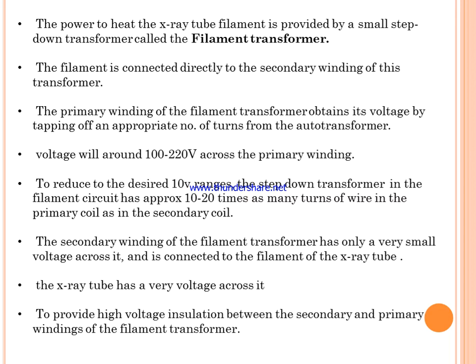Power to heat the X-ray tube filament is provided by a small step-down transformer called the filament transformer, and the filament is connected directly to its secondary winding. The primary winding obtains voltage by tapping off an appropriate number of turns from the auto transformer — around 100 to 220 volts. The step-down transformer in the filament circuit has approximately 10 to 20 times as many turns in the primary coil as in the secondary coil.